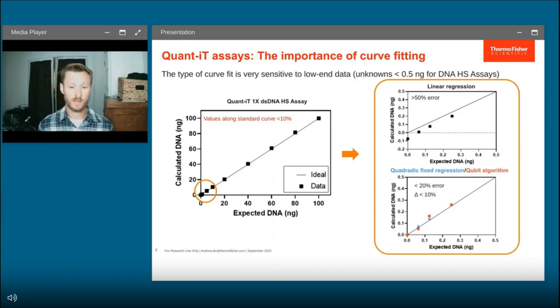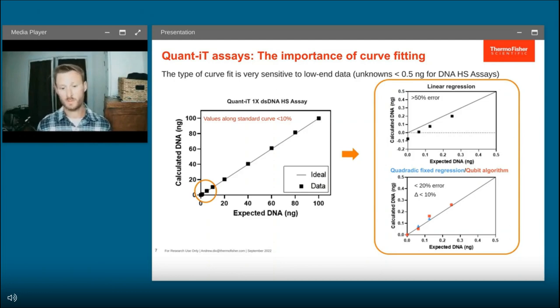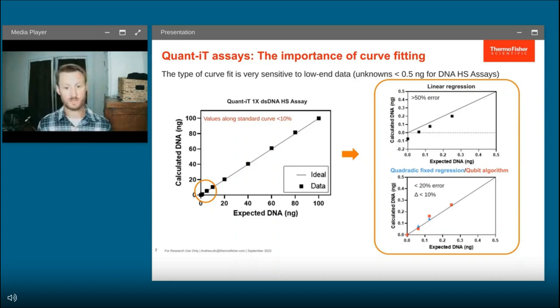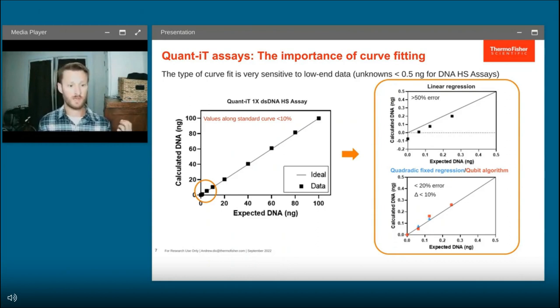We strongly recommend using background correction and ideally a quadratic model. Background correction can be done by simply subtracting the blank from all your samples and fixing the y-intercept to zero. Alternatively, you can set your y-intercept to the RFUs of your blank measurement — for example, if that's 23, set it to 23. This will tidy up your data at the low end and allow you to get within about 10% of expected concentration, consistent with what you'd expect from a Qubit fluorometer measuring the same samples.